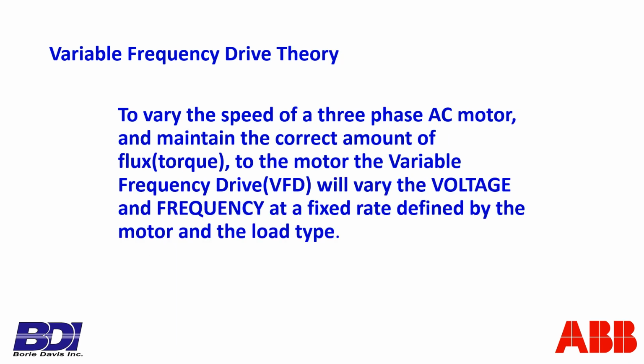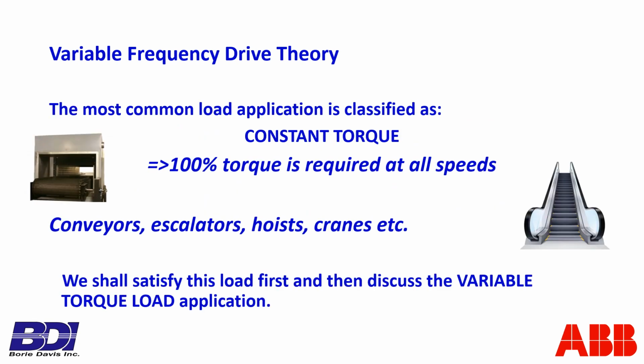To vary the speed of a three-phase AC motor and maintain the correct amount of flux, or turning force, torque, to the motor, the variable frequency drive will vary the voltage and the frequency at a fixed rate defined by the motor and the load type. Okay, so we're going to talk about a couple of different load types. The most common load application is classified as constant torque. That's your conveyor systems or your escalators or your hoists or your cranes. Constant torque means 100% torque is required at all speeds from 0 to 60 hertz.